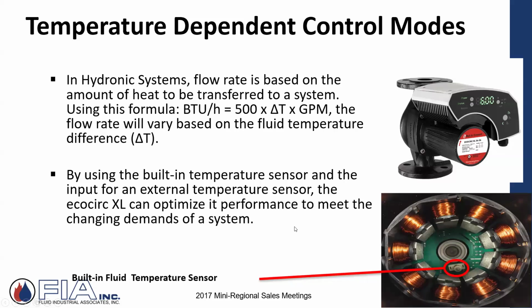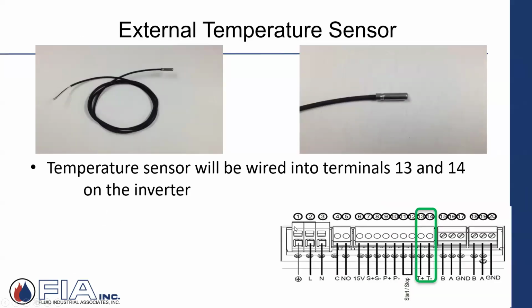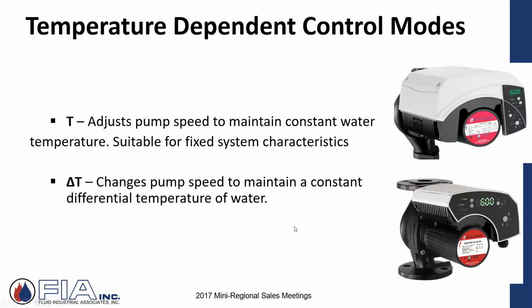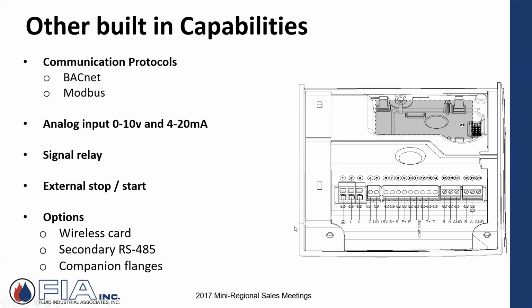Temperature is another mode, temperature dependent. In the pump itself, in the dry section, right behind the impeller, there's a built-in temperature sensor. So if you add an external sensor, you could do delta T temperature control, another option. So it could be this guy right here, delta T: onboard temperature sensor, and then the remote, and I can do supply return. It's an option. One last thing that we take advantage of all the time is it has the ability to receive an external, in this case, analog input, 0 to 10 volts DC or 4 to 20 milliamp input. And it becomes speed control.